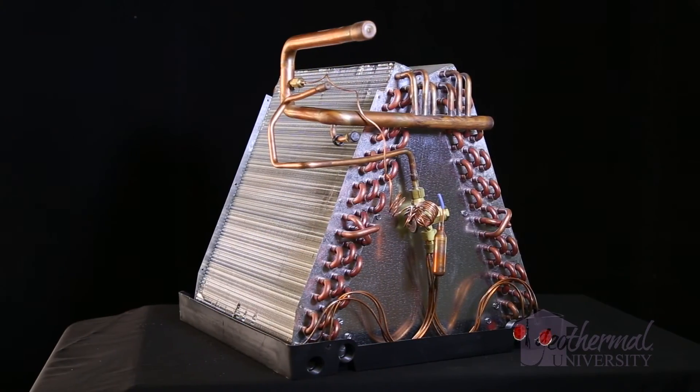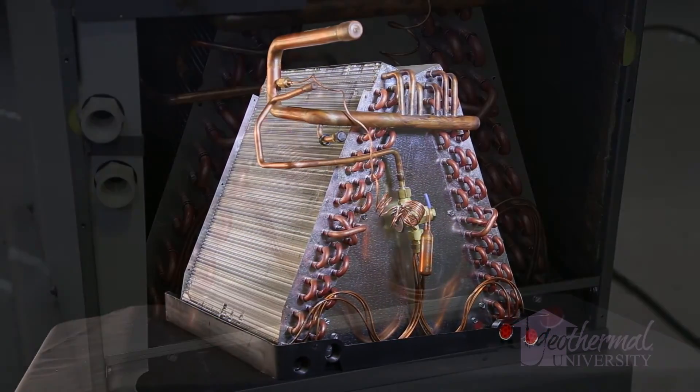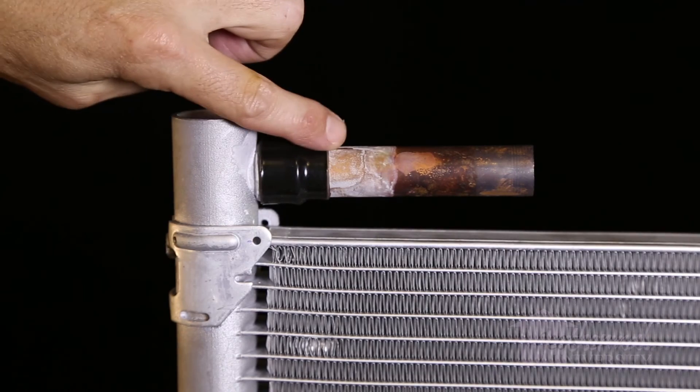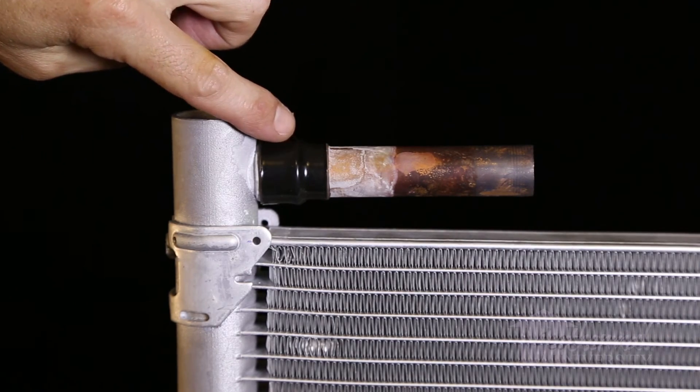If the equipment is newer, perhaps failed on startup, it's likely a solder joint, mechanical connection, or transition piece. This could have been caused by manufacturing, transportation damage, or vibration.